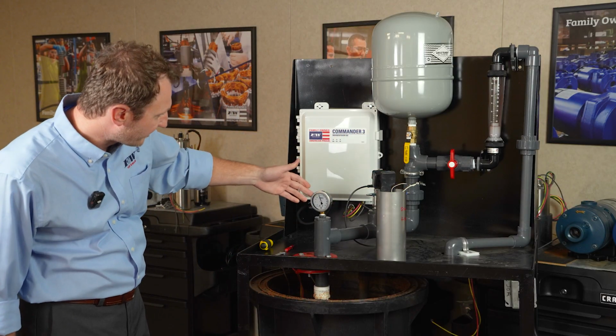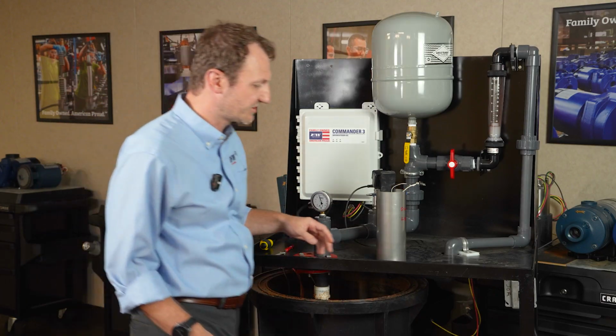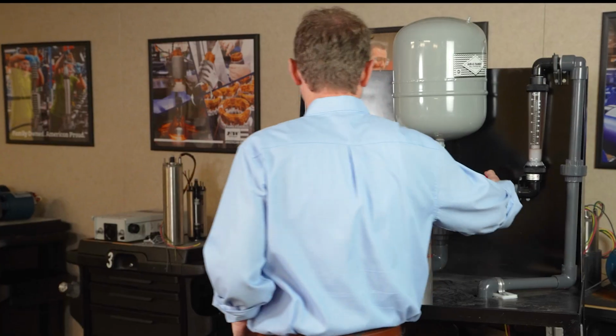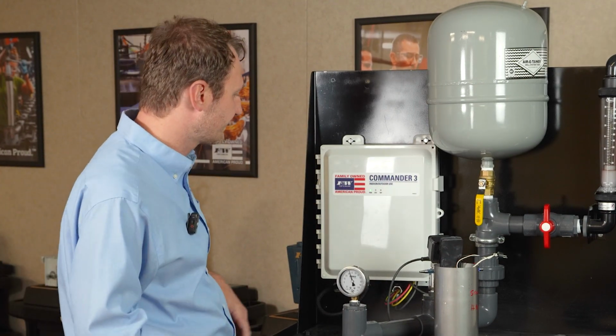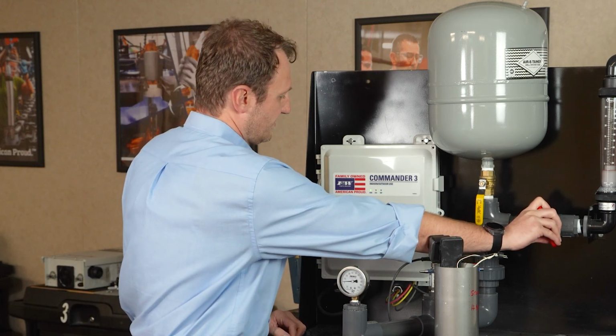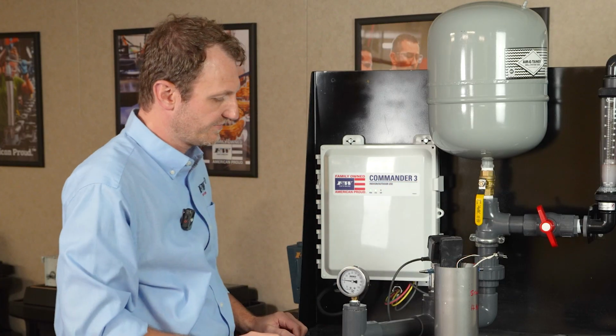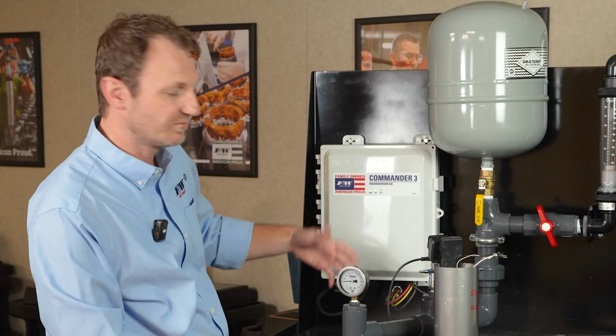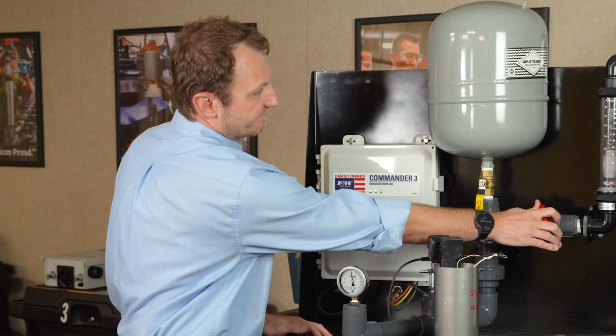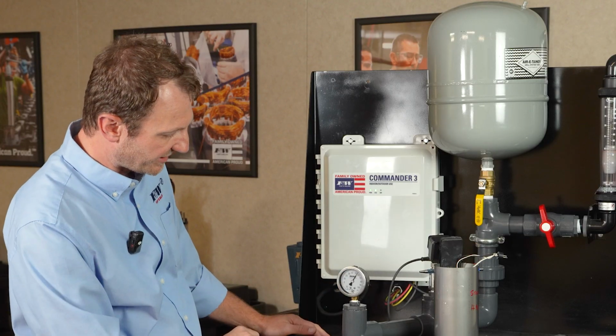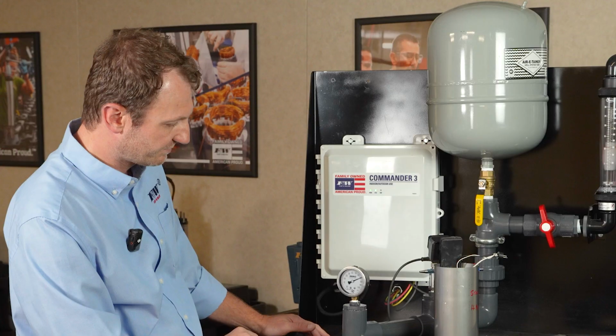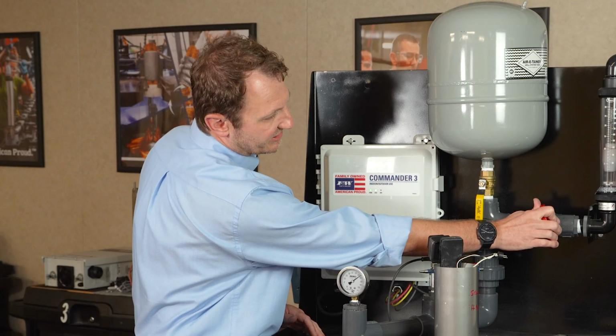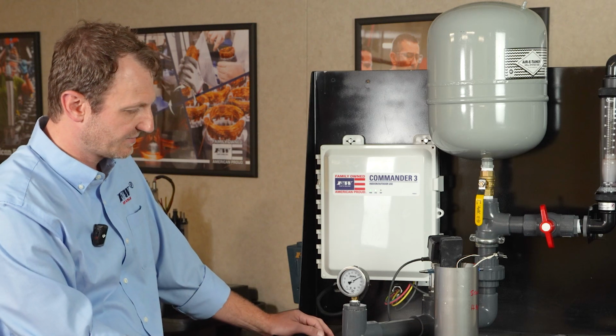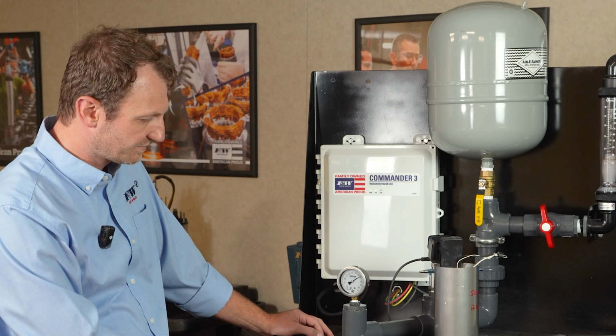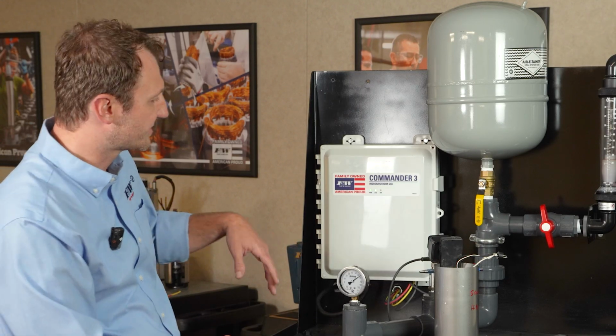We've got about, looks like a little bit of pressure here in the line. We'll go ahead and kick it on and see what she does. Power light's gonna blink here. Status is indicating that we're running the motor. See our pressure running up here. Running about 10 gallons a minute. We'll cut her back just a little bit. We're getting a little closer to that 60 PSI here.